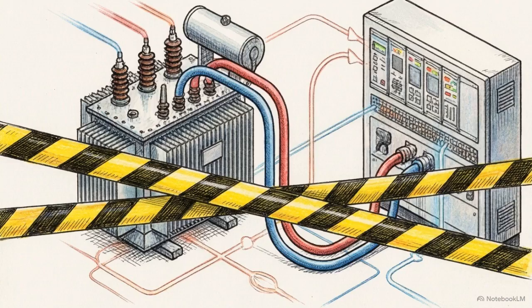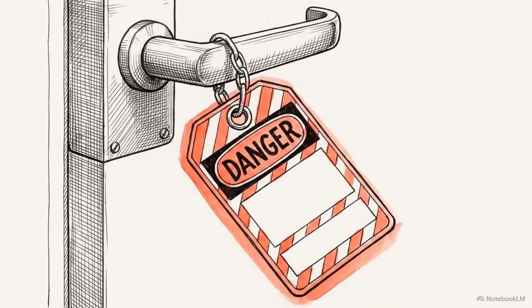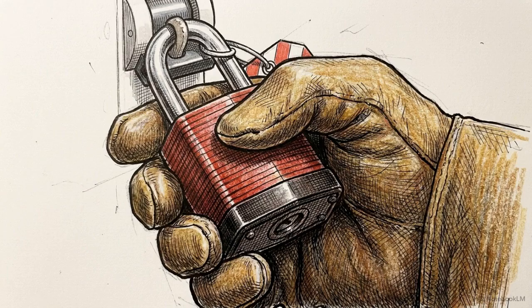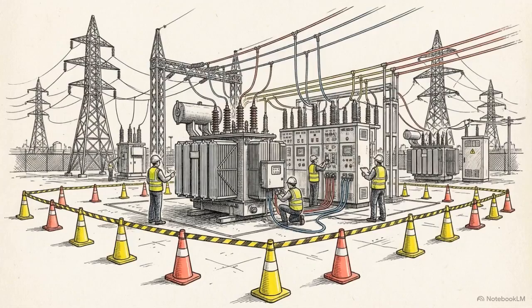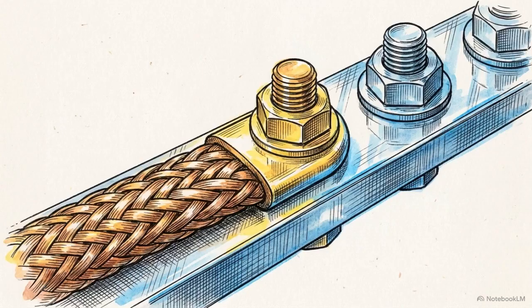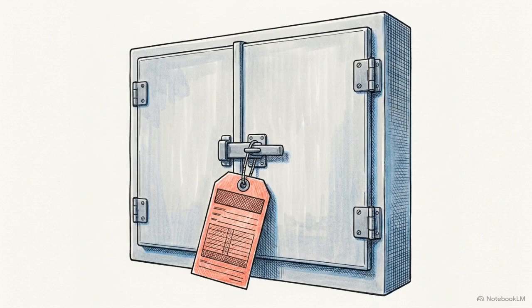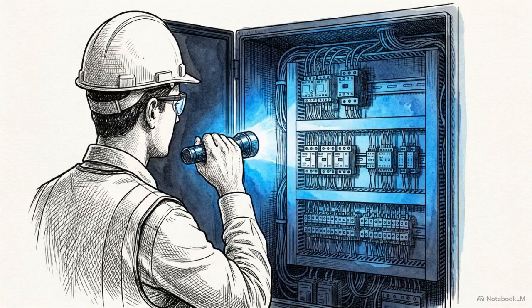But before any logical testing can legally begin, we must establish the primary safety prerequisite. Absolute physical safety must be secured. This requires the strict execution of lockout and tagout, or LOTO protocols. Equipment is locked out, safety warning boundaries are established, and proper grounding is physically verified before any panel is ever opened. Once safe, we begin the initial visual inspection phase.